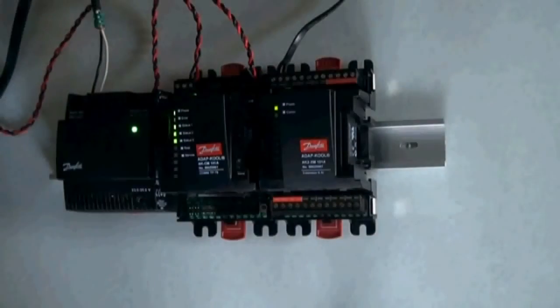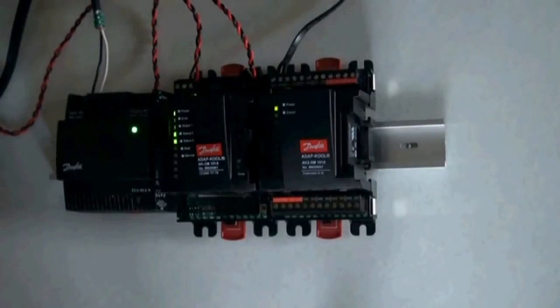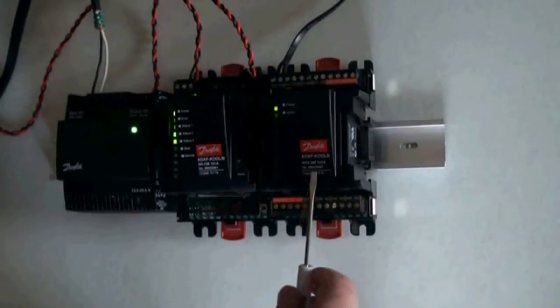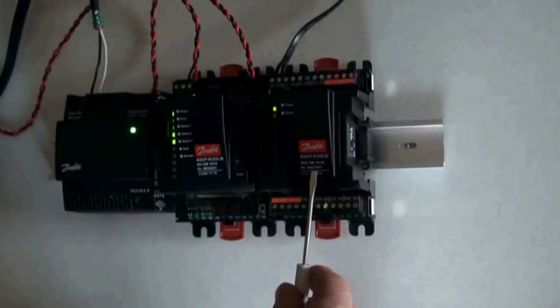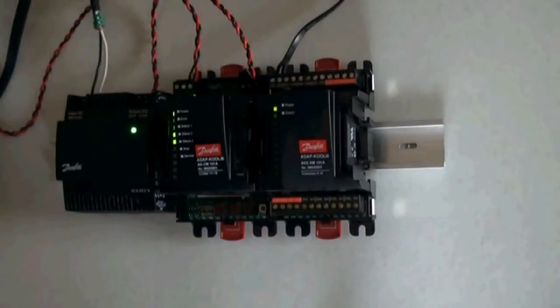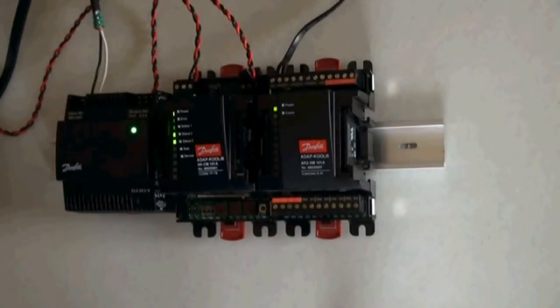Next we'll cover replacing or adding an AK2 module. Note that on each AK2 module the part number can be found here, should it be needed. The first step is to depower the communications module. This is an important step, otherwise the module could be damaged.